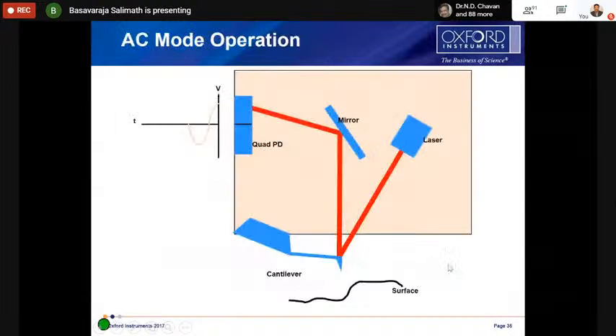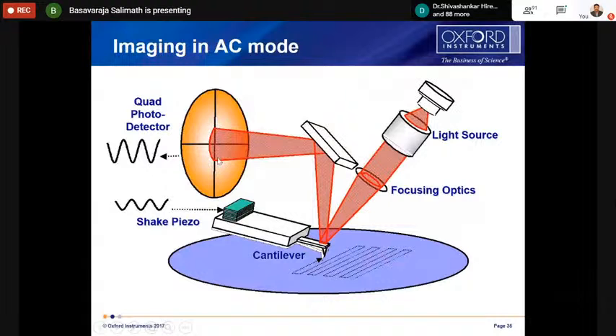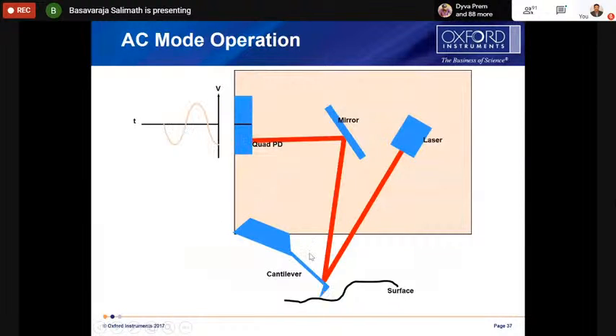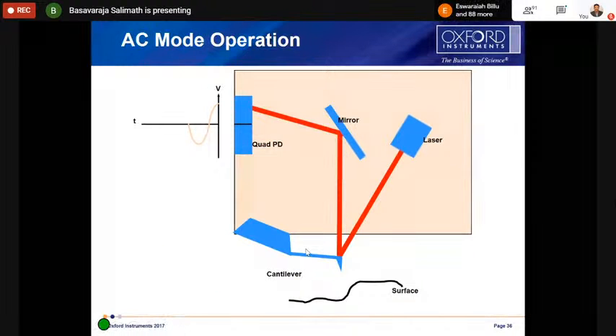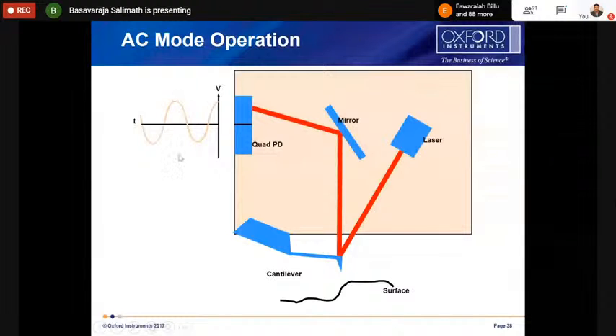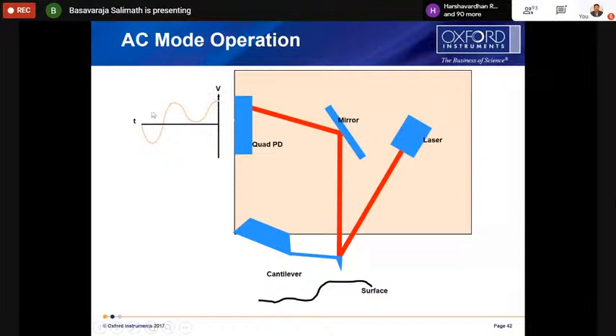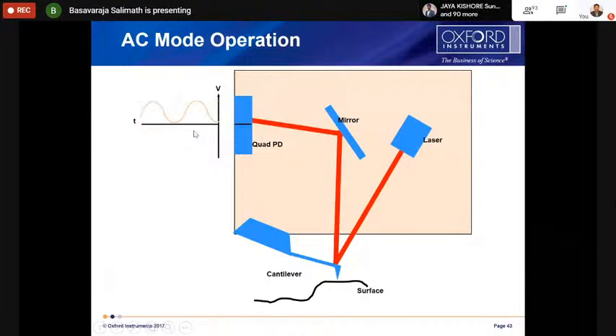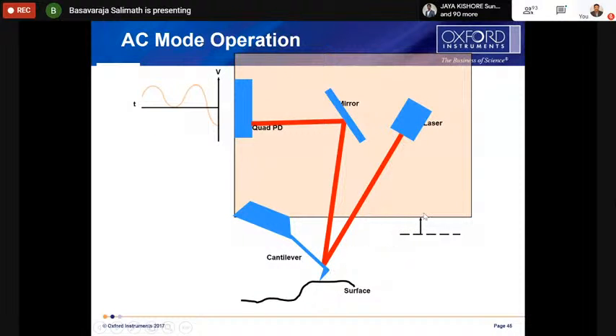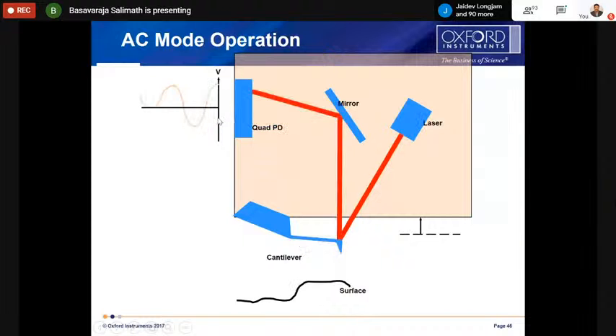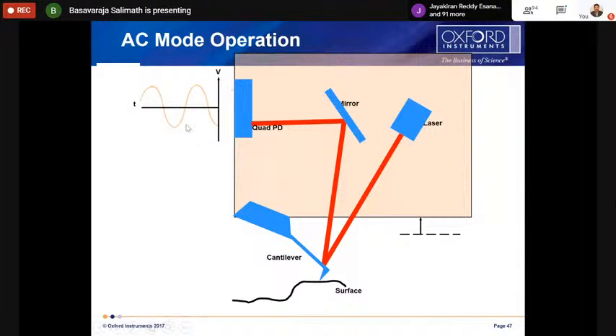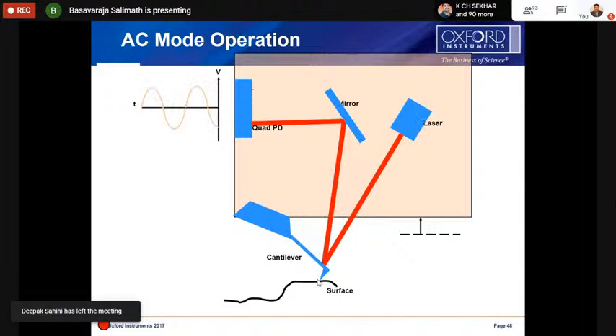Now, when this is oscillating, the laser spot in the photodetector will also be oscillating. You can see this is how it is oscillating. It has to maintain this amplitude constant. But when it goes from here to here, you can see the amplitude becomes very small, and it has to maintain the amplitude while scanning. So it will adjust the tip height again, and you can see the amplitude becomes bigger, whatever it was initially. So like this, it is monitoring the amplitude of the tip oscillation, and then it gives us the images in the case of tapping mode or semi-contact mode.